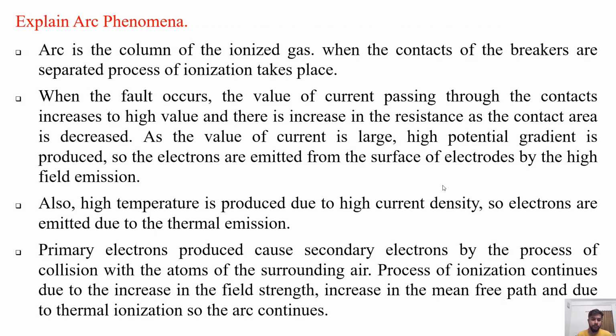Explain arc phenomenon. Arc is the column of ionized gas. When the contacts of the breakers are separated, process of ionization takes place. When the fault occurs, the value of the current passing through the contacts increases to a high value, and there is an increase in resistance as the contact area decreases. As the value of current is large, high potential gradient is produced. So the electrons are emitted from the surface of electrodes by the high field emission. Also high temperature is produced due to high current density. So electrons are emitted due to the thermal emission.